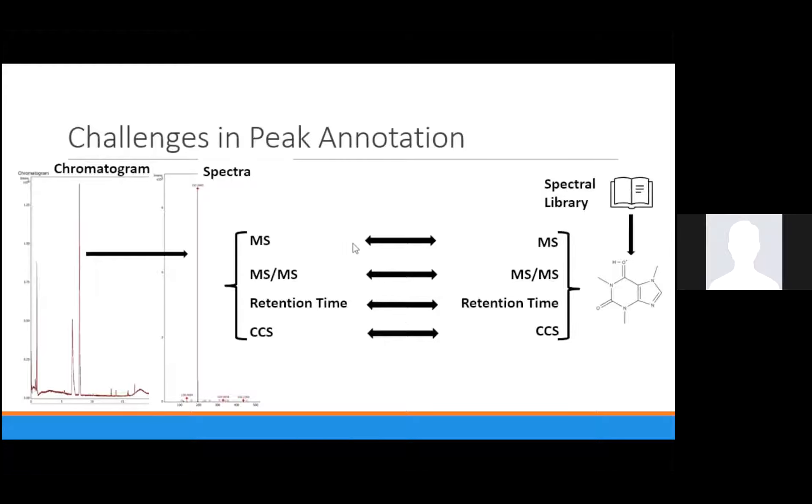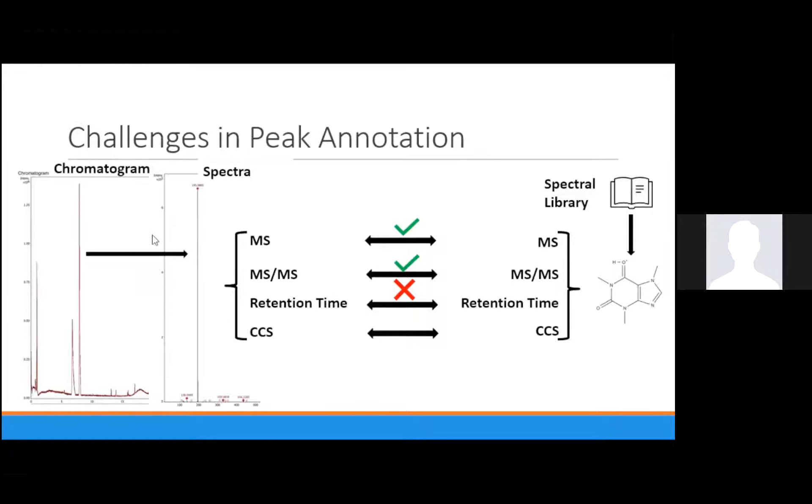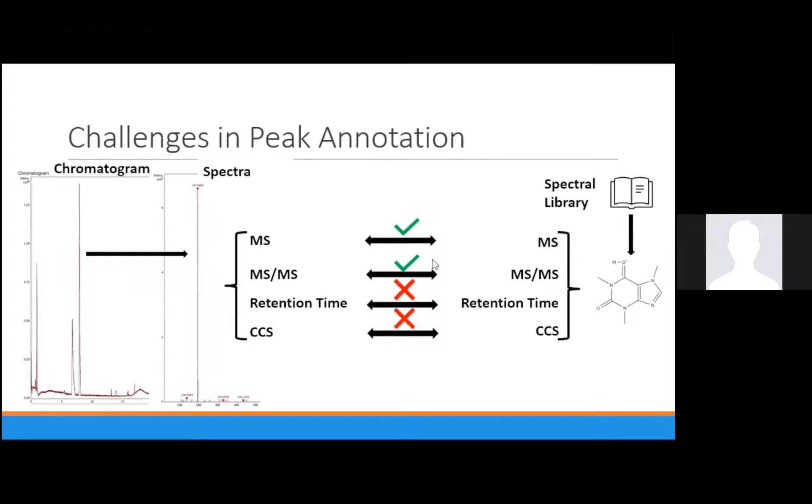Peak identification algorithms are constantly improving, as are the spectral libraries for peak annotation. These libraries have a database of fingerprints from authentic standards that can be compared to sample data. Identification failures occur when these data do not sufficiently match. For example, MS1 is usually available, but not always sufficient. MSMS is the most valuable data, although this can vary by fragmentation technique. Retention time is often useless, unless samples are ran on the same column between your authentic standards and your sample data. CCS is really useful if you can get it, but most spectral libraries do not contain any CCS data, as the instruments that can collect it are fairly recent.